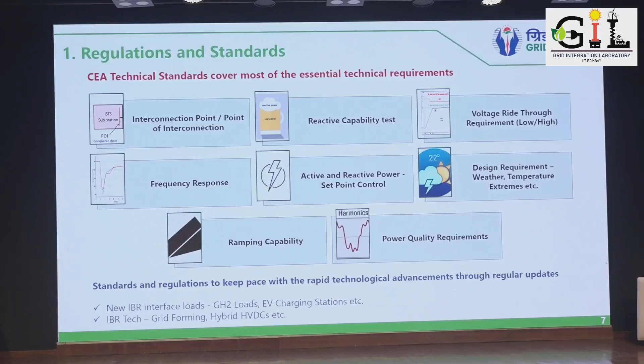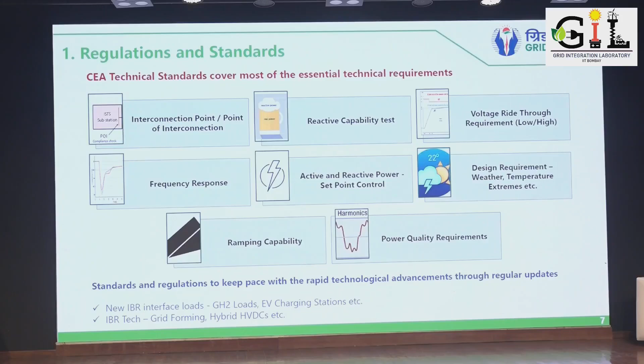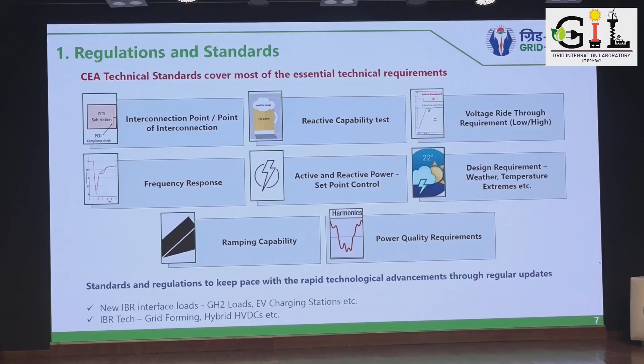And when large-scale RE comes in the Ladakh area, the low temperature issue has to be taken care of. Frequency response: presently in our grid code and CEA standard, plants of more than 500 megawatts should have the capability to take the signal from the remote. But each and every plant should have at least this capability. When in future it comes into a grid code, state grid code, or national grid code, that they need to provide ancillary services, they can always be hooked up. But this functionality needs to be there, that based on the frequency signal, they should be able to ramp up or ramp down their generation.